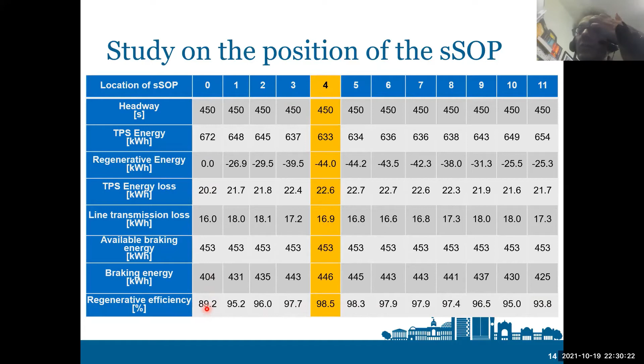In our study, we went more in depth into understanding the best position of the SOP. We looked at a sample line with 11 substations, studying the power flow using the train simulator. It is possible to obtain the substation where the regenerative braking energy is maximum, compared to the case with no SOPs, where recuperation is around 90%.